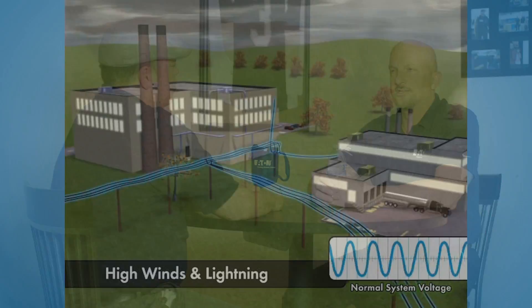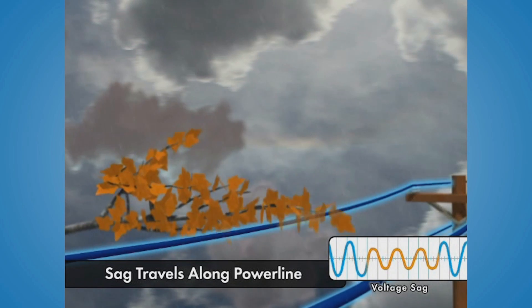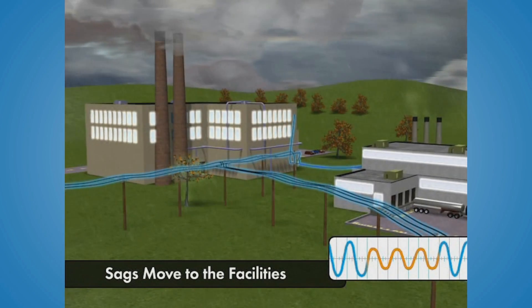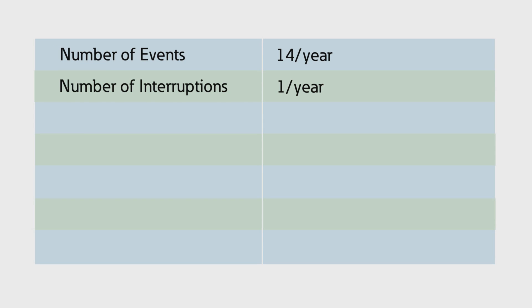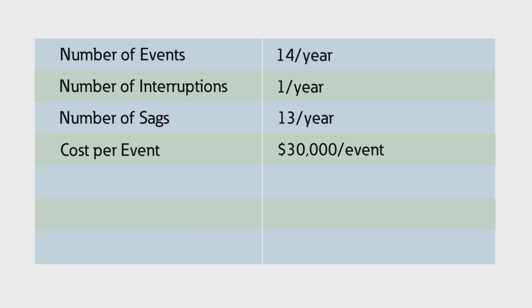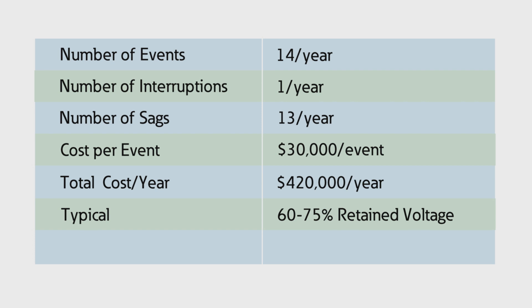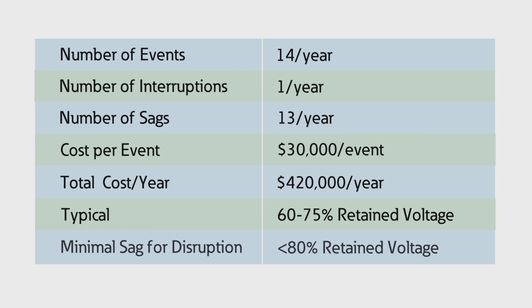Why are sags considered the most costly PQ event? Basically because they generally affect a majority of your facility or process. A 7x24 plastics plant was very diligent about monitoring their power system and had identified that over the past five years they averaged 14 deep voltage sags that caused disruption. Only one of the 14 on average was a full interruption. They identified losses of $30,000 per event as a result of seized equipment and the associated cleanup. The 13 sags had a typical range of 60 to 75% retained voltage, and a sag over 80% retained voltage wouldn't disrupt their process.